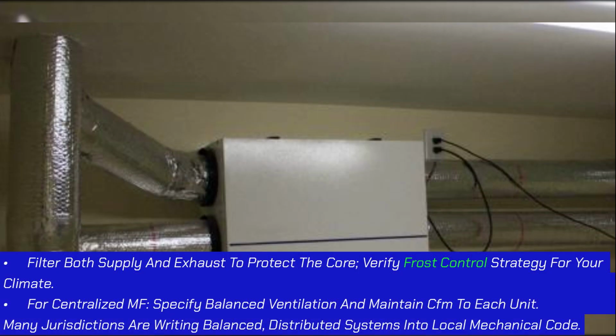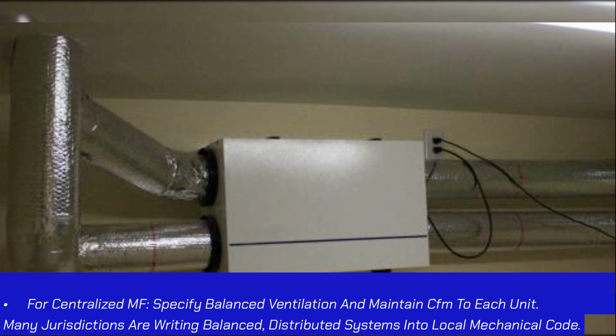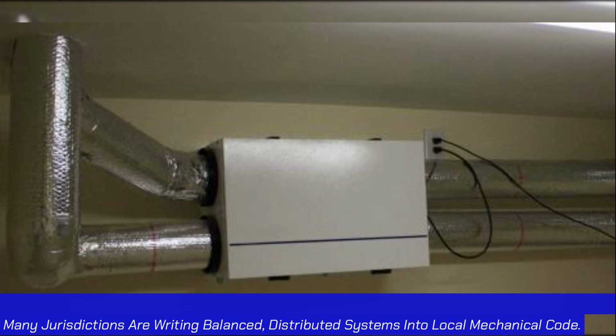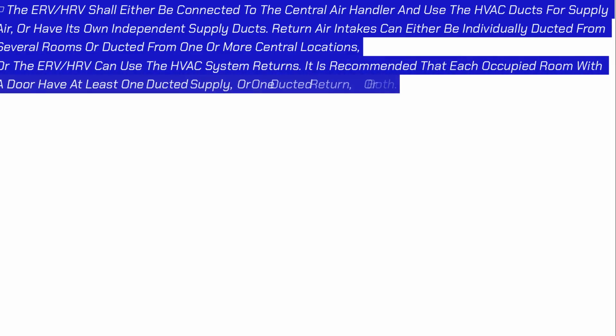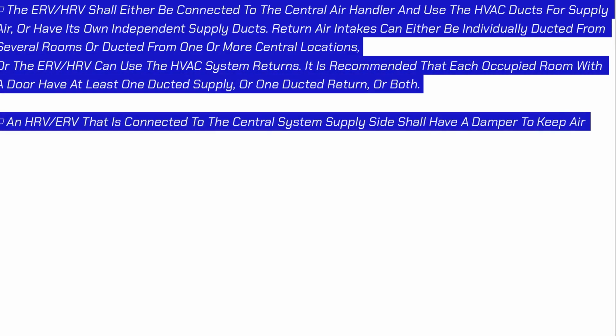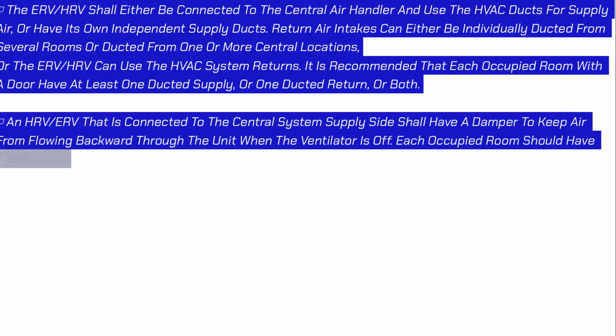For centralized MF, specify balanced ventilation and maintain CFM to each unit. Many jurisdictions are writing balanced, distributed systems into local mechanical code. The ERV, HRV shall either be connected to the central air handler and use the HVAC ducts for supply air, or have its own independent supply ducts.